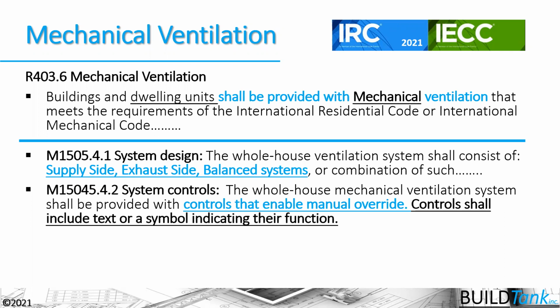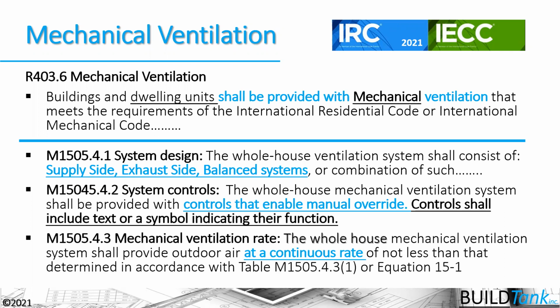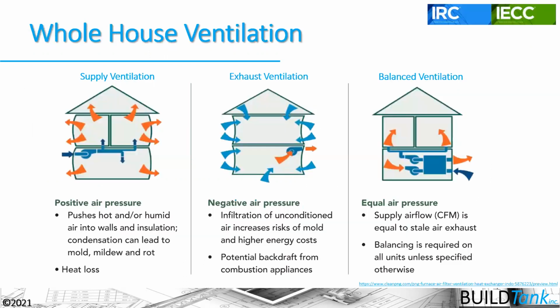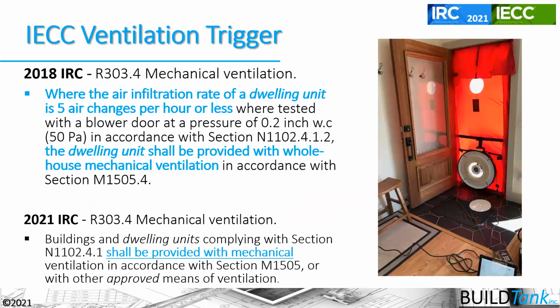But now the code, this other underlying section here, says controls shall include text or a symbol indicating their function, which is super important because we don't want people turning off these systems and not turning them back on. We want them to understand why they're turning them off and why they should be running. And then again, the mechanical ventilation rate is super important. So again, it doesn't matter if you install supply ventilation, exhaust ventilation, or balanced ventilation, but you have to decide what rate you're going to turn it onto and when you need it.